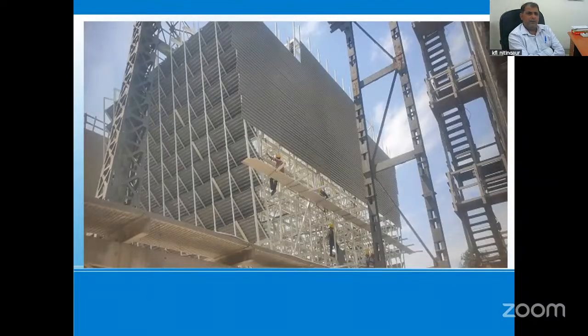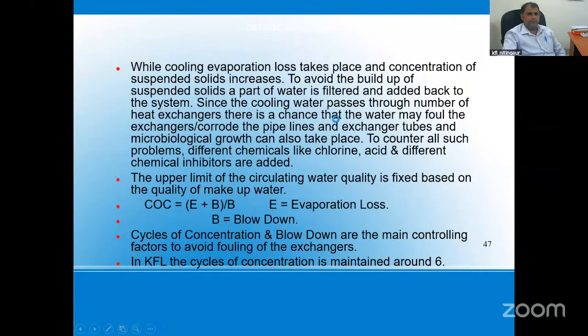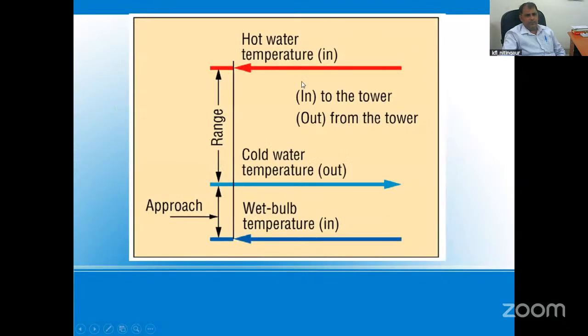And now, due to limited resources of wood and timber, all plants have replaced the timber with pultruded FRP material. This is the inside view of the cooling tower. Cooling tower performance depends on these two factors: range and approach. Range is the difference between the hot water temperature and the cold water temperature. We try to cool down the water to its wet bulb temperature.